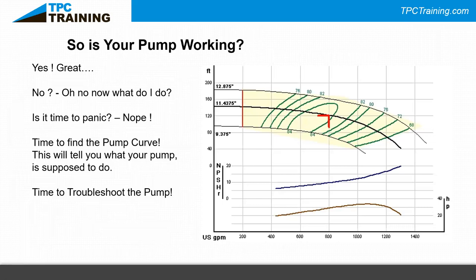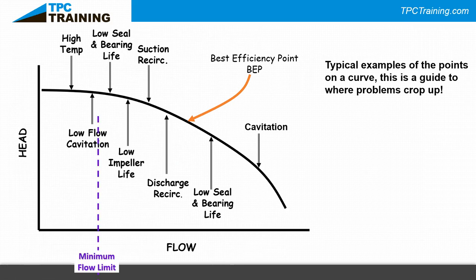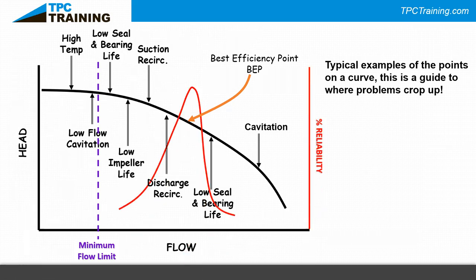The pump was in runaway — trying to move more fluid than it was capable of. When it was over, I asked how long the old pump had lasted — about 11 or 12 years. But in the original application the pump was 300-400 feet away from the tank. When they added on to the plant they moved the pump right next to the tank. A lot of problems crop up when someone moves a pump without redoing the friction and resistance calculations.